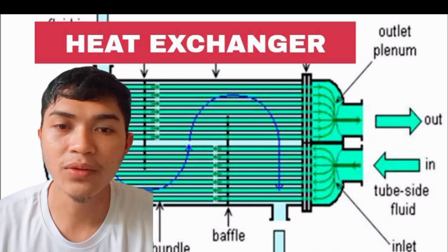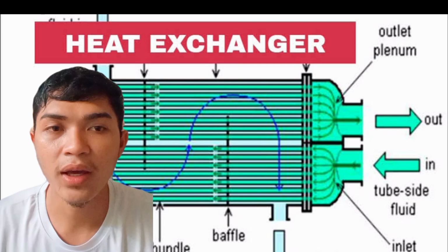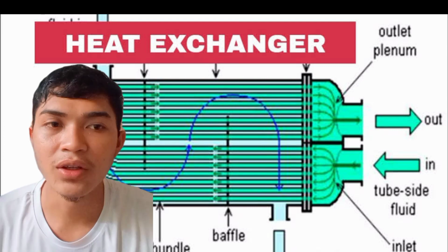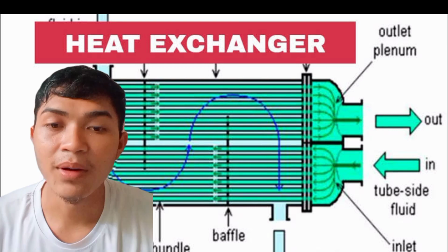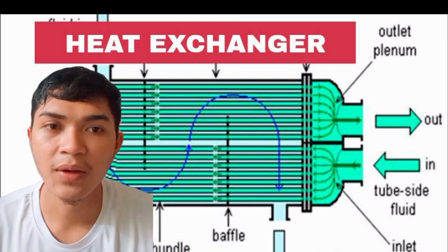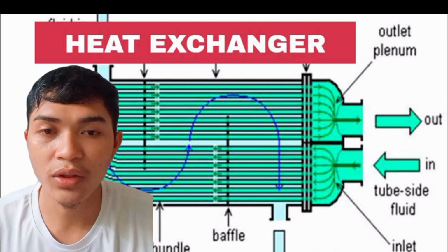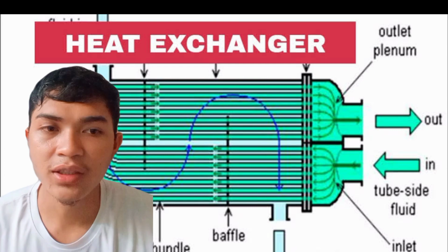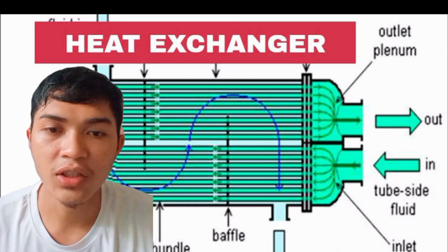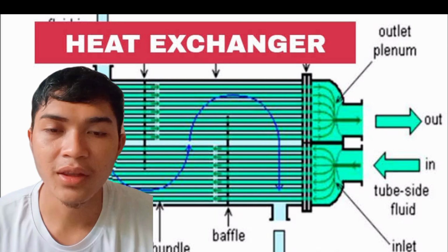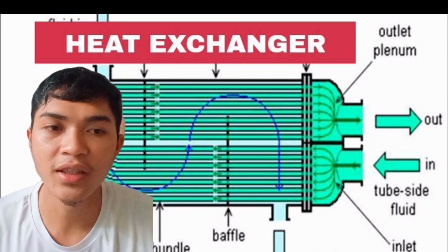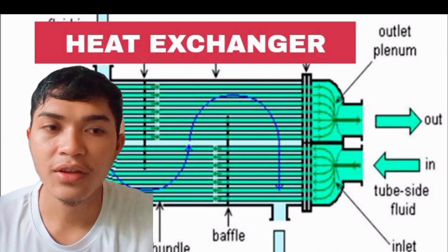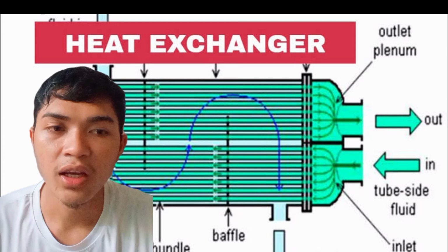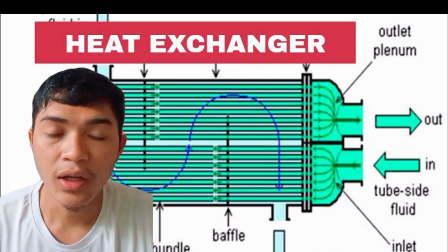Along with mediums such as fresh water, air, and oil, seawater is also used abundantly in marine heat exchangers as an important cooling source. However, because of the presence of dissolved salts in seawater, corrosion and scale deposits are a common condition in heat exchangers. Maintenance of marine heat exchangers is therefore necessary at regular intervals of time to prevent reduction of heat transfer or failure of equipment.